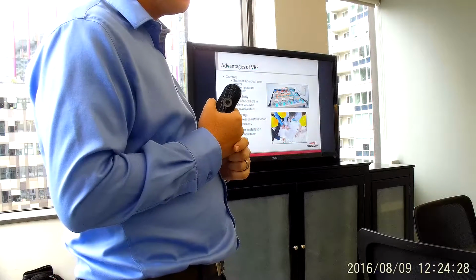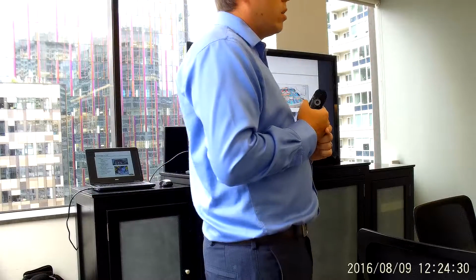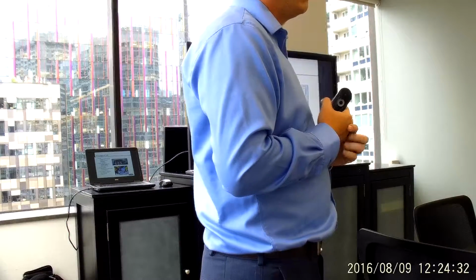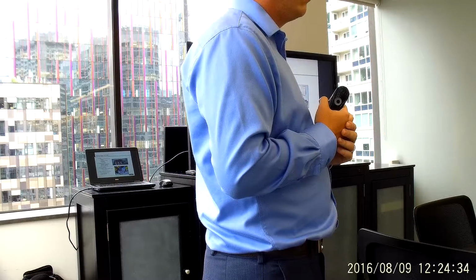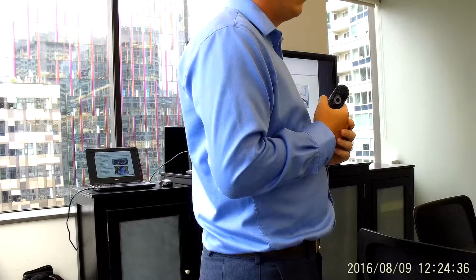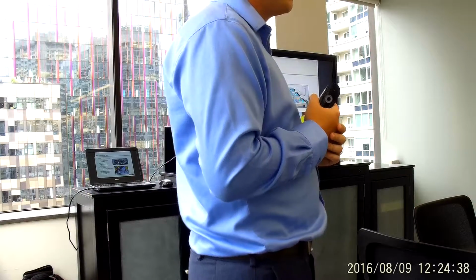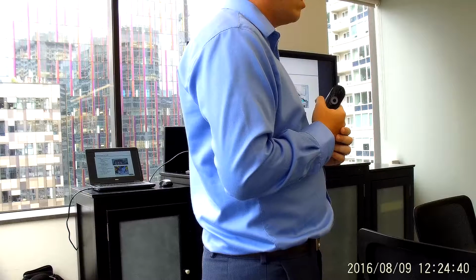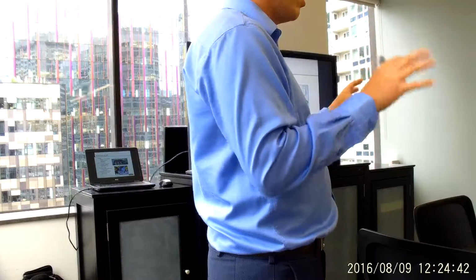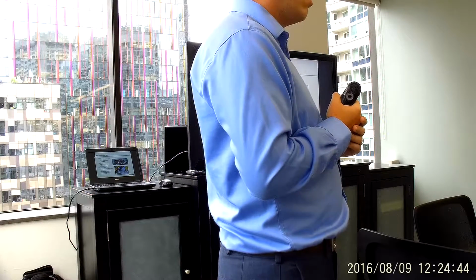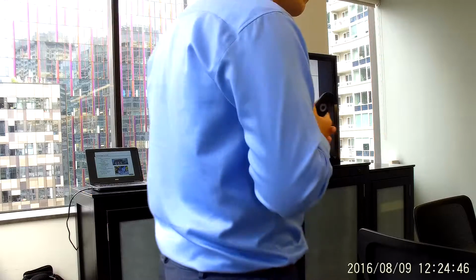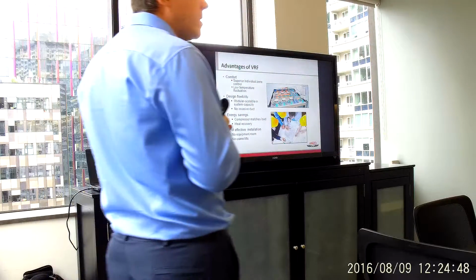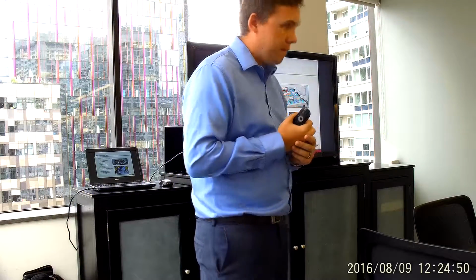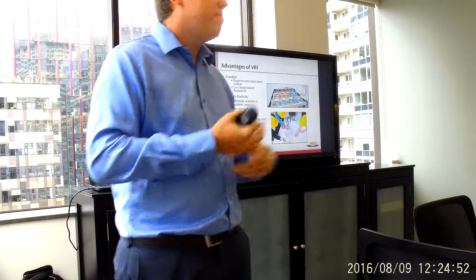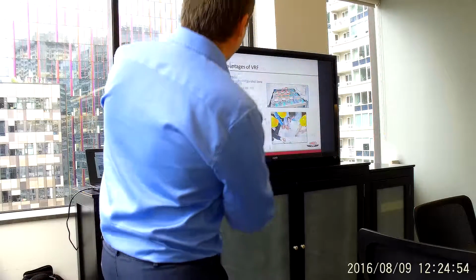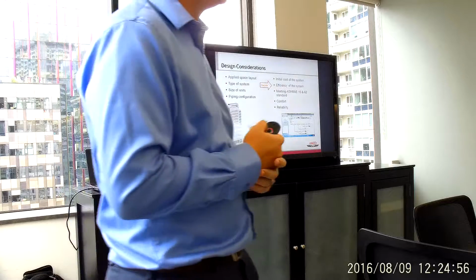While you're on that topic, what are the issues with dealing with the refrigerant requirements of the International Mechanical Code? Are you talking about ASHRAE 15? The volume I'm talking about is refrigerant, Chapter 11 of the IMC, about the pounds of refrigerant per 1,000 cubic feet of room volume. Yeah, that triggers my very next slide - machinery room and ASHRAE 15 refrigeration.